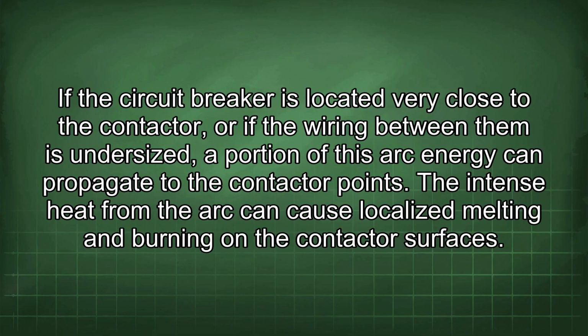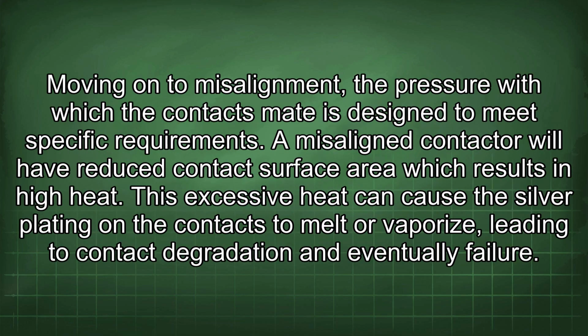If the circuit breaker is located very close to the contactor, or if the wiring between them is undersized, a portion of this arc energy can propagate to the contactor points. The intense heat from the arc can cause localized melting and burning on the contactor surfaces. Moving on to misalignment, the pressure with which the contacts mate is designed to meet specific requirements. A misaligned contactor will have reduced contact surface area, which results in high heat.